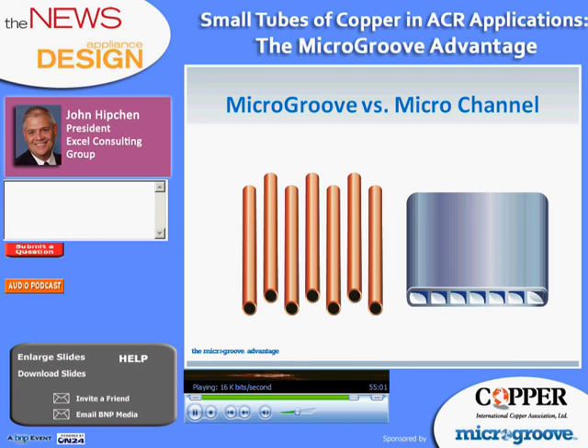And then in the area of refrigerant charge reduction, the researchers at Midea Refrigeration Appliances Group, they conducted performance experiments, and they did that with R410A and also R290. And those tests were done on split air conditioners with small diameter 4mm tubes. And without sacrificing any performance, the 4mm tubes reduced the volume and cost of the heat exchanger and significantly lowered the refrigerant charge.